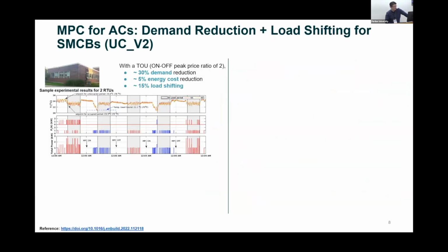And next, we added the load shifting capability to version 1, which was the demand reduction. And this one was tested with laboratory buildings having 2 rooftop units. Again, thermostat temperature, and also each compressor's power and the total power summation. And the shaded area is when the electric price is high, basically the on-peak price period. And the test signal we used is an on-peak to off-peak price ratio of 2. And the red one, again, is conventional control, the blue one is model predictive control. We're switching back and forth daily in this case.